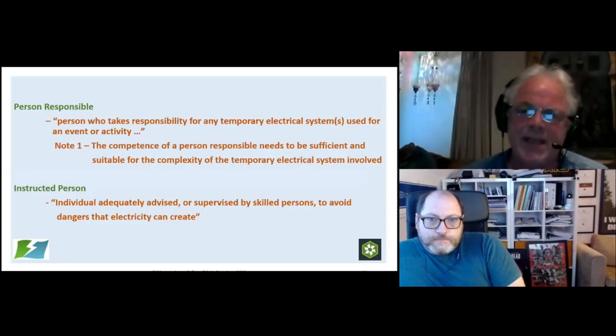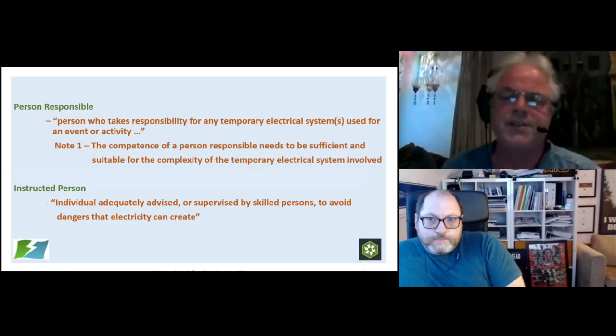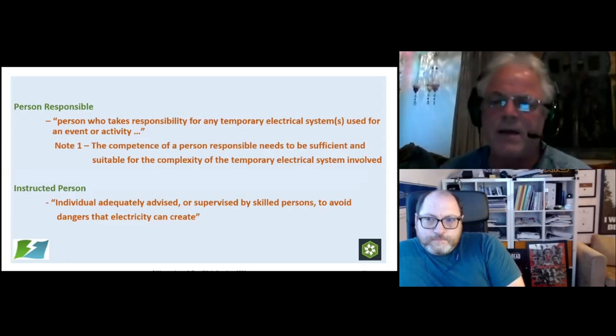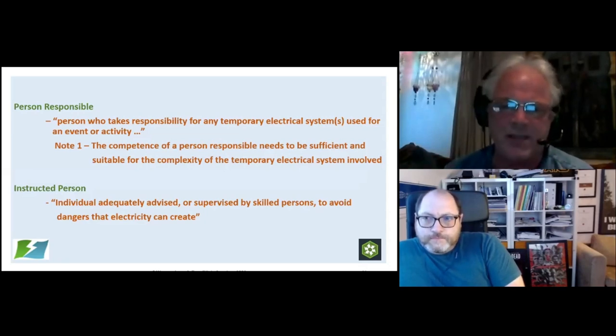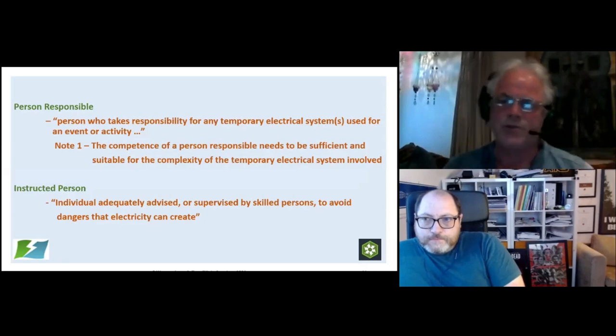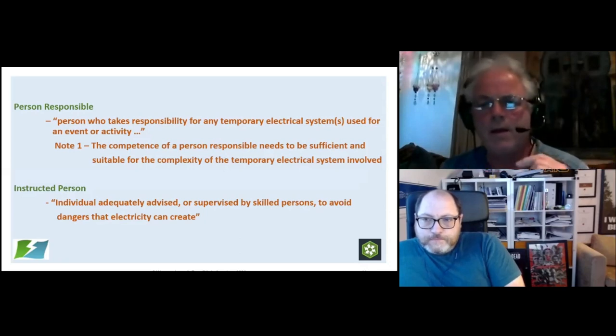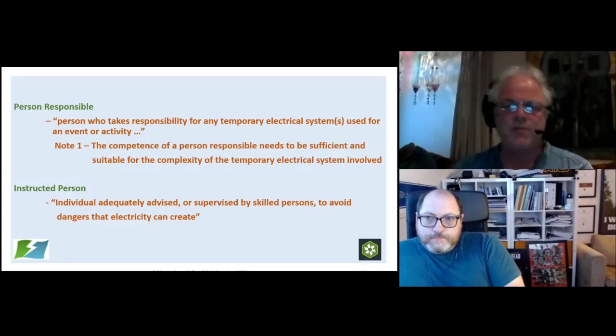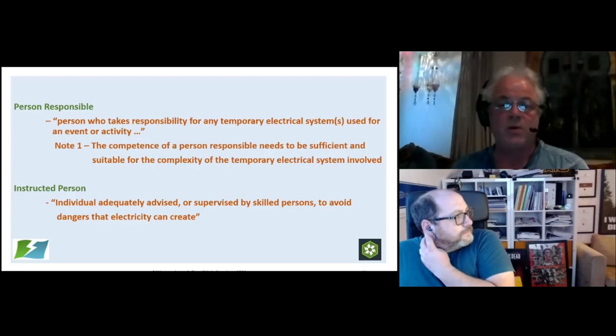They're competent. They need to be suitably competent for the system involved. And this is where BS7909 breaks down temporary systems into certain sizes. It talks about small systems, it talks about large systems. Small systems is anything up to 6 kVA, so we're looking at about 26 amps, a couple of 13 amp extension leads. Up until that point, they talk about it being a small temporary electrical system. For a small system, the person responsible for that doesn't need to be a fully qualified electrician. It can be somebody who's just got a bit of common sense.